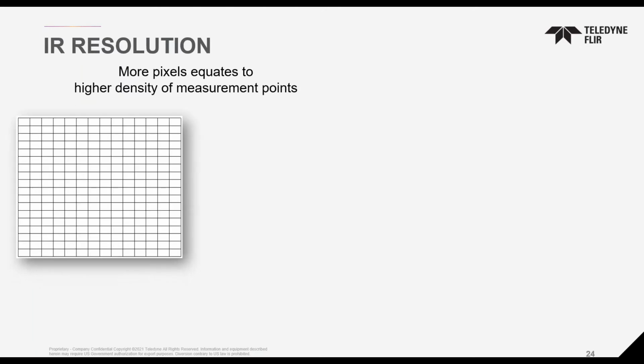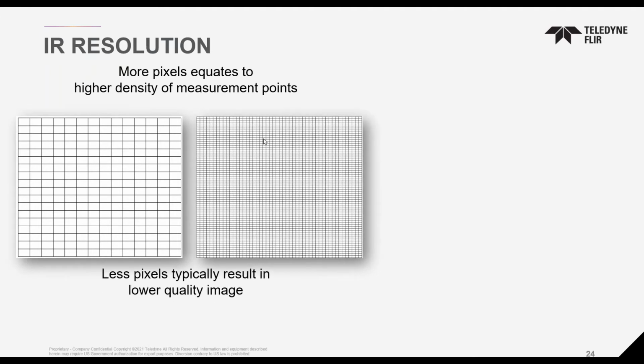One of the biggest things to take into account when looking at thermal cameras is the IR resolution. This box on the left, this big box with the grid inside, might be a somewhat low density IR resolution. The one now on the screen is a higher density, or more pixels in that same space. The two main boxes are the same size, but now we have a lot more pixels inside that same space. The more pixels you have, the higher density of measurement points you'll have, the more accurate your reading will be, and the more temperatures you'll be able to pick up.